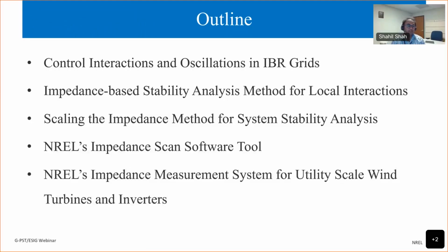So here is the outline of this talk. First, I'll talk about control interactions and oscillations in IBR grids, then move on to impedance-based stability analysis method for local interactions. So this will be a standard method, which is used for understanding the local interactions. And then I'll talk about scaling the impedance method for system stability analysis, how we can scale that to understand stability of a larger power system with high amounts of inverter-based resources, which is the main topic for today's talk. And then I will talk about NREL's impedance scan software tool. And depending on how much time I have at the end, I'll talk about the impedance measurement system for utility scale wind turbines and inverters that we have developed at NREL.